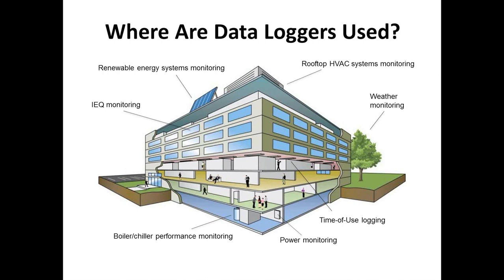We can look at boiler chiller performance monitoring, so we can install ultrasonic flow meters and actually look at chilled water flow through a pipe, while also monitoring supply temperature, return temperature, power used by an electric chiller, and also power monitoring and IEQ monitoring. We can look at things like CO sensors, CO2 sensors, to tell us if it's a good opportunity for demand controlled ventilation, and also get creative with it and use it for things such as determining occupancy.